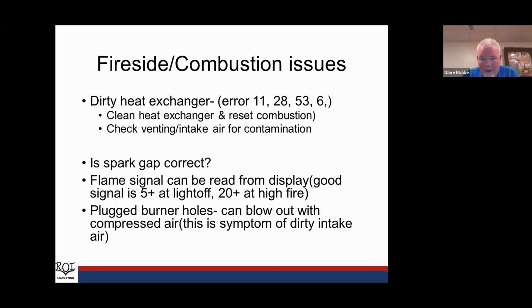Again, plugged burner holes. We can blow that out with compressed air. If you have that, that's a symptom of dirty intake air. So there's something going on externally, whether it's pollen or dust. I had one that was sawdust. The boiler was installed in a cabinet shop. Everything was good for the first year. Something changed, we went out, and we found the burner all plugged up. It turns out they got a new dust collection system. And where do you think their dust collection exhaust went? Right out where our boiler intake air was. So that was an issue.